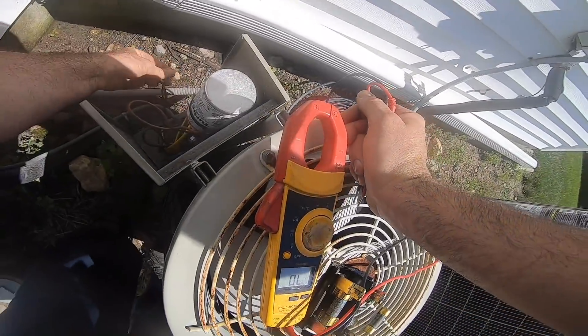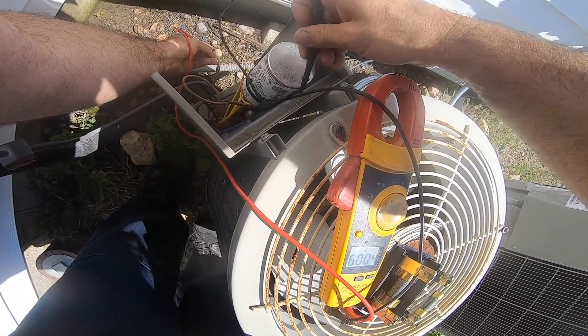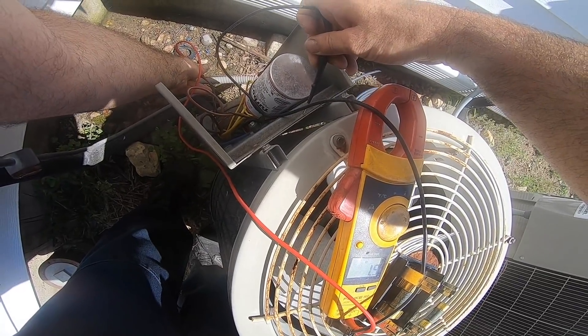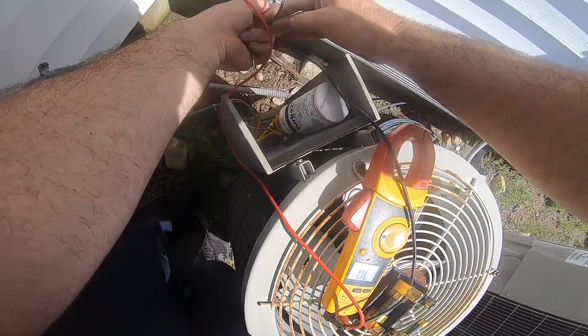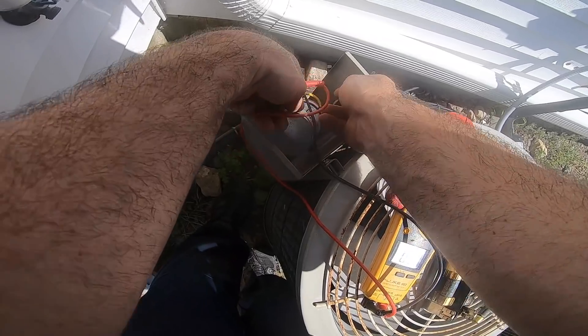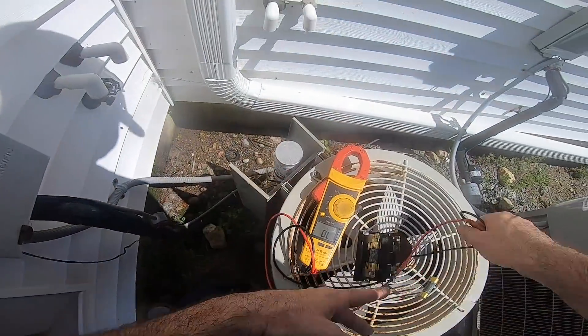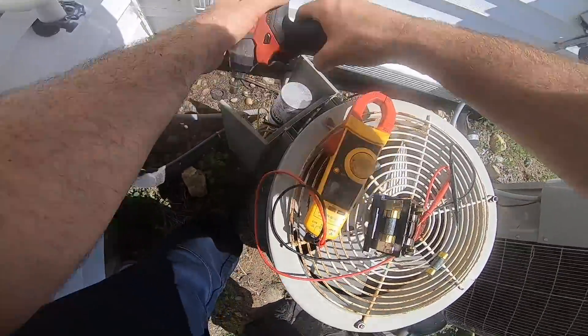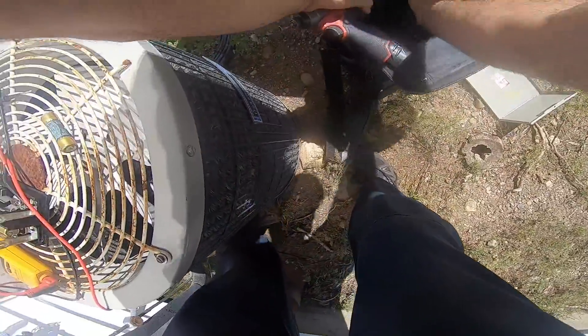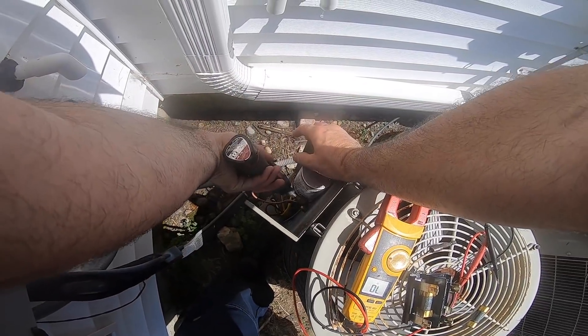I want to swap that contactor - I dislike it. Let's see the compressor stuff. Going blue and black. Got something going on. Let's just check this compressor out, make sure it's not shorted - this way I'm not putting a fuse in for it to blow.